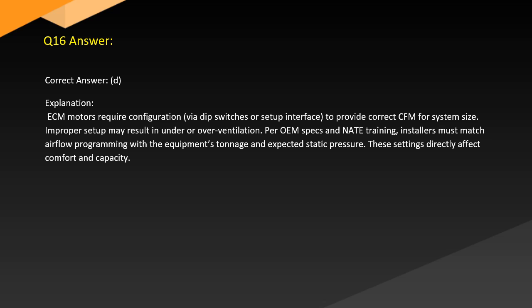Answer. Correct answer: D. Explanation. ECM motors require configuration via dip switches or a setup interface to provide correct CFM for system size. Improper setup may result in under or over ventilation. Per OEM specs and NATE training, installers must match airflow programming with the equipment's tonnage and expected static pressure. These settings directly affect comfort and capacity.